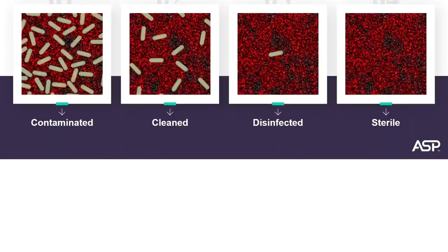According to the Association for the Advancement of Medical Instrumentation, AAMI, as we know it, the Bible or the go-to gold standard for reprocessing items, ST91, which focuses on flexible and semi-rigid endoscope reprocessing in healthcare facilities, notes that high-level disinfection is frequently used to reprocess endoscopes. Flexible endoscopes are cleaned at the point of use immediately after each procedure, followed by manual cleaning and high-level disinfecting using chemical disinfectants. At minimum, it is recommended that devices are subjected to HLD after each use. But when possible and practical, flexible and semi-rigid endoscopes should be sterilized due to the greater margin of safety built into sterilization.